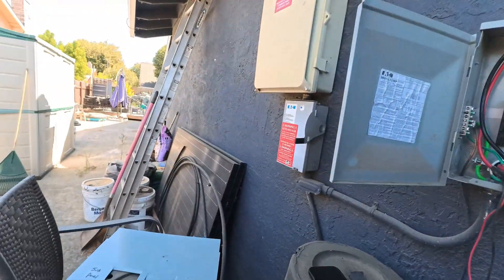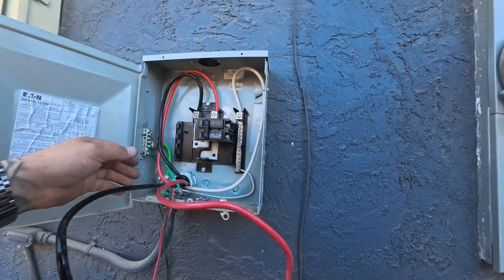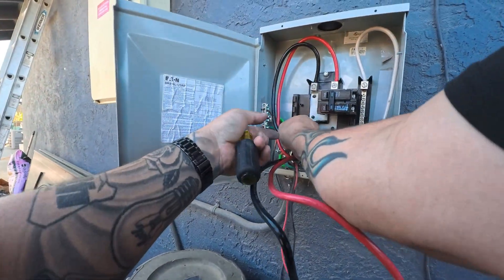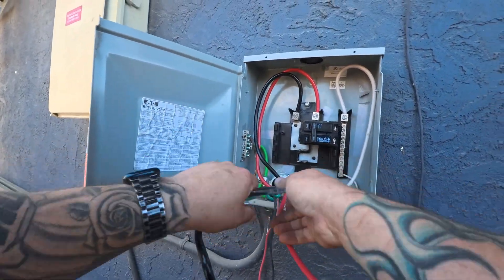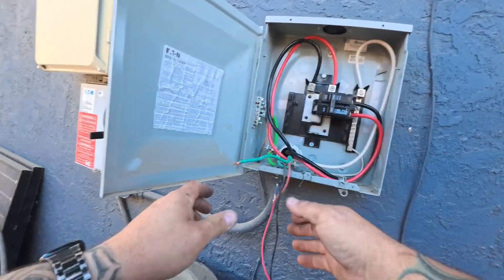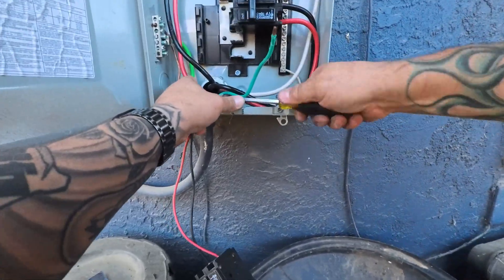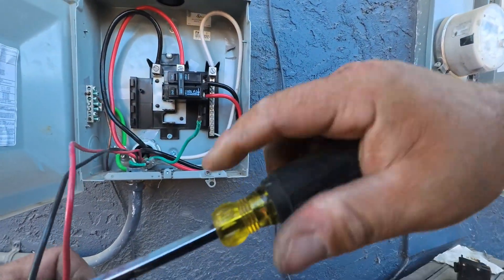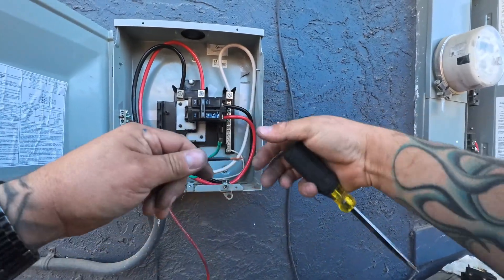Just like that. That was even tight — but you could literally just pull that wire right out. Solar guys strike again. Let me trim that down a little bit. Look at how loose that is. There's a little piece of copper not seated all the way.